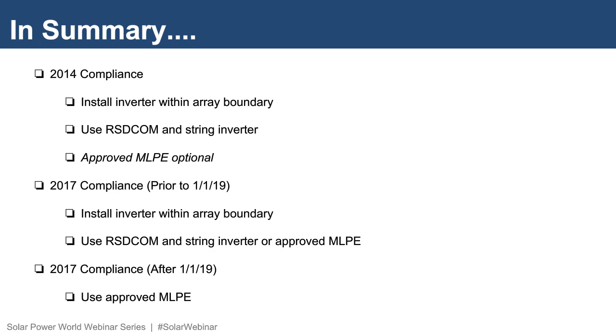If you're in a 2017 jurisdiction prior to January 1st of 2019, again, you can install the inverter within the array boundary. This will allow you to meet the array level rapid shutdown. Or use an RSDCOM combiner box coupled with the string inverter and again approved MLPE. A year and a half from now, January 1st, 2019, to comply with the 2017 code, an approved MLPE device will be required, unless the installation is a building integrated PV system, as Eric introduced previously.